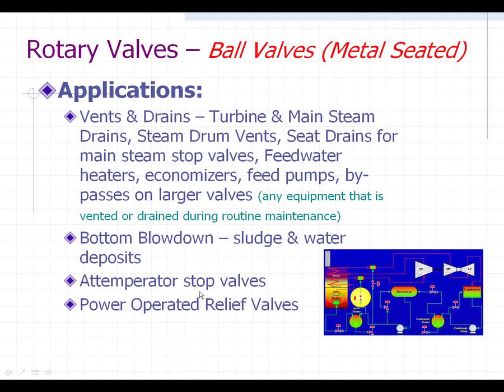You can also use them as attemperator stop valves in front of a desuperheater or in front of a spray valve on your attemperators. They can also serve as isolation valves on both sides of a control valve, even something as large as a startup or main feed regulator, and they work very well in those applications.